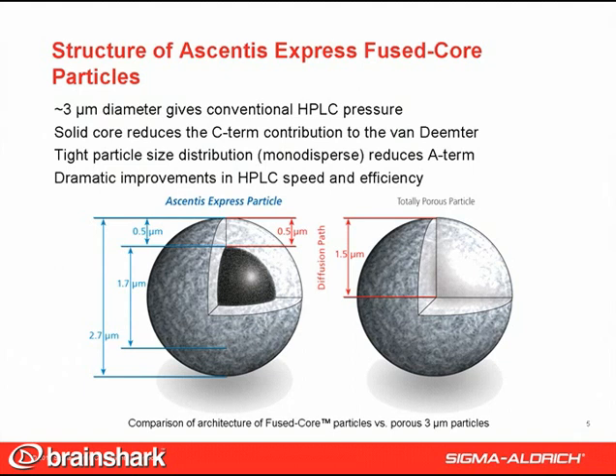So how do Ascentis Express columns achieve high-speed and high-efficiency separations on any HPLC, UPLC, or UHPLC system? It's all about the structure of the particle, its unique solid core design. This slide shows what we mean by fused core. The drawing on the left is a cutaway of a fused core particle, and on the right is a standard totally porous particle that has been used for HPLC since the 1970s. The Ascentis Express particle is about the same size as a 3-micron totally porous particle, so it gives roughly the same pressures as a 3-micron particle. This has speed implications — you can run these columns at much higher flow rates on conventional instruments than you can run a sub-2-micron particle column.